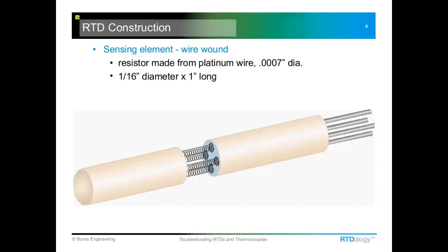First off, RTD — Resistance Temperature Detector Construction. This is what we call a wire-wound sensor; it's one of the more common styles. It's a ceramic tube, and we make little coils of platinum wire and thread them inside the tube, then attach external lead wires. The internal wires are 7 ten-thousandths of an inch in diameter, so as you can imagine, they're fairly fragile. They have to be supported somewhat so that during shock and vibration they're not moving around too much, but if tied down too much that can put strain on the wire and cause a resistance shift.